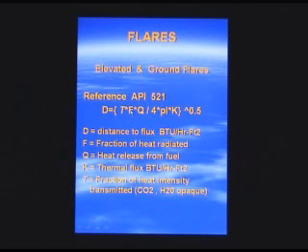along with tau, F, Q, and all the other parameters. So that would tell you how far away you have to be from that flame in order to satisfy a 200 BTU per hour per square foot flux from that. For North Slope applications, since the sun is so far away, we basically ignore solar radiation, and that allows us to get a little bit closer to the flame.